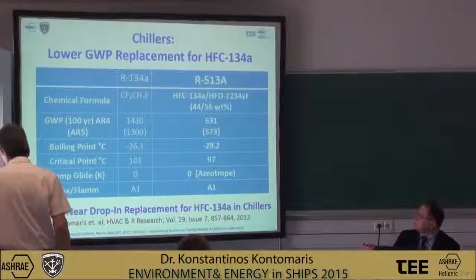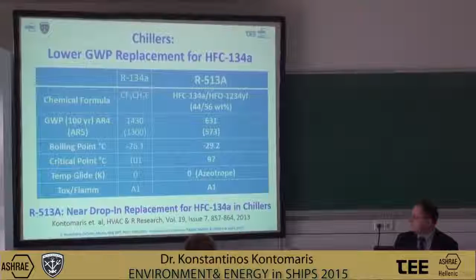Although it is a blend, it is a truly azeotropic blend, which has zero glide, which also explains the 500 designation of this fluid. This is significant for chillers because it's a requirement for the efficient operation of the large flooded heat exchangers of large chillers. And it also has a safety classification of A1, which means low toxicity, no flammability. Bottom line, this new fluid is a near drop-in replacement for 134A again.